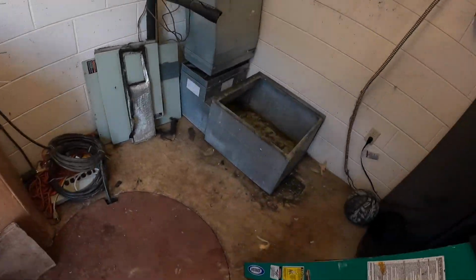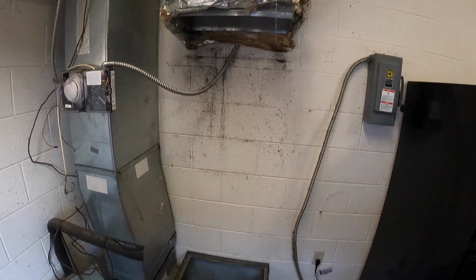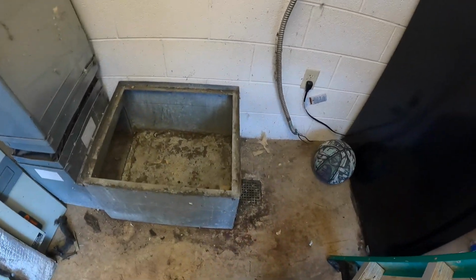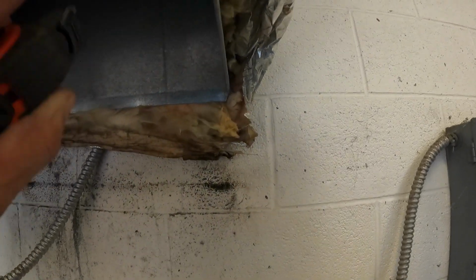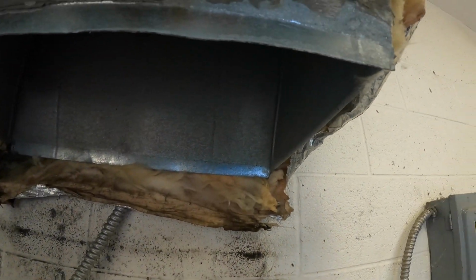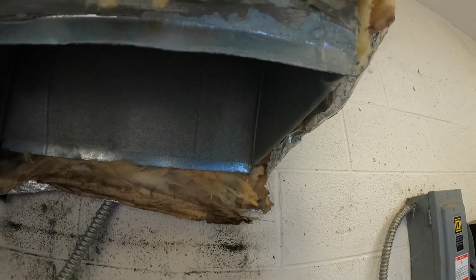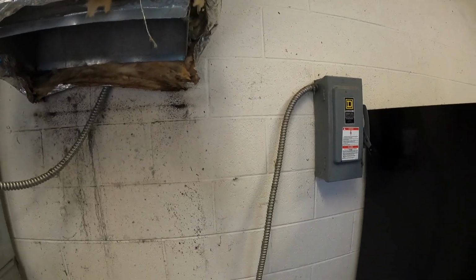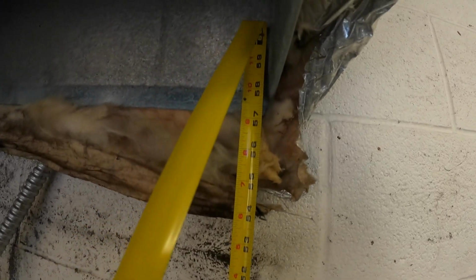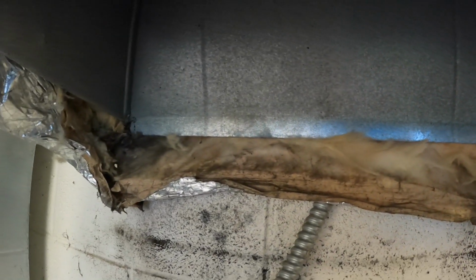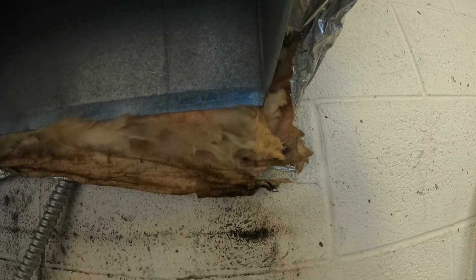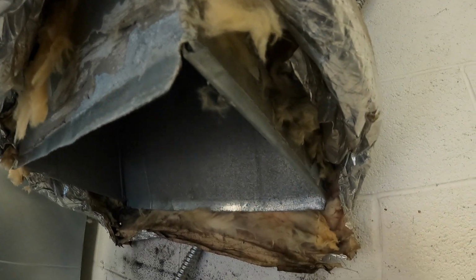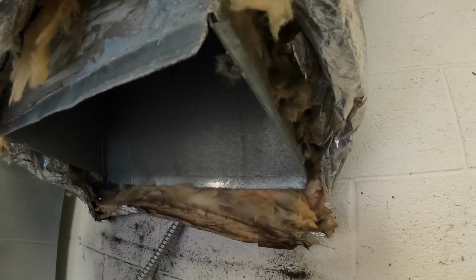All right, she's outside. And now we need to see how tall that is from the plenum up to the supply duct here, and see what we have to do to make 58 inches fit in there. And it looks like 58 is right to where the S-lock used to be. So we can probably make that thing fit pretty good. May have to bend these drives down and trim them off or something, but I think it's not as bad as it could have been.